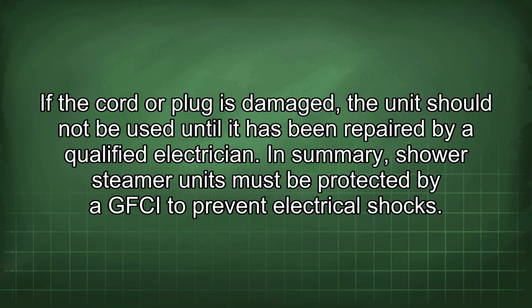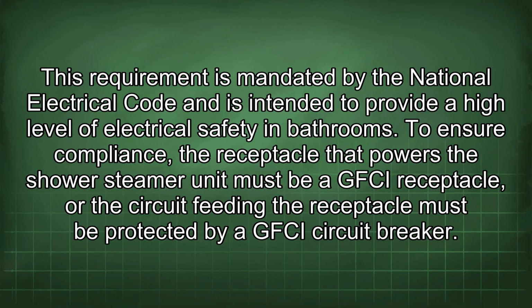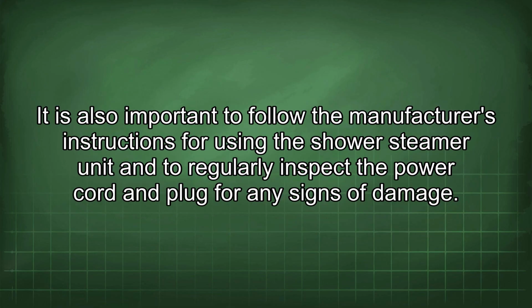In summary, shower steamer units must be protected by a GFCI to prevent electrical shocks. This requirement is mandated by the National Electrical Code and is intended to provide a high level of electrical safety in bathrooms. To ensure compliance, the receptacle that powers the shower steamer unit must be a GFCI receptacle, or the circuit feeding the receptacle must be protected by a GFCI circuit breaker. It is also important to follow the manufacturer's instructions for using the shower steamer unit and to regularly inspect the power cord and plug for any signs of damage.